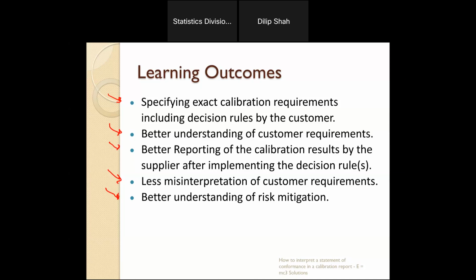So this is not a new thing, but it's been around for a while, but there's more emphasis put on the 17025 standard. The current standard came out in 2017. And the reason for that is technology is getting better and better. We have better and better instrumentation available to us, and the standards to calibrate those instruments are not keeping pace. And so at the end user level, we have better and better instruments. The standards are not keeping pace with us.